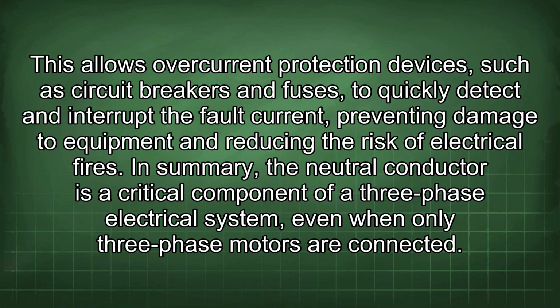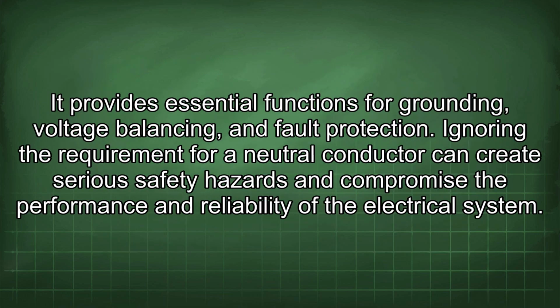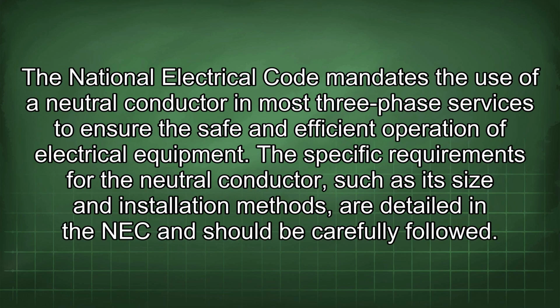In summary, the neutral conductor is a critical component of a three-phase electrical system, even when only three-phase motors are connected. It provides essential functions for grounding, voltage balancing, and fault protection. Ignoring the requirement for a neutral conductor can create serious safety hazards and compromise the performance and reliability of the electrical system. The National Electrical Code mandates the use of a neutral conductor in most three-phase services to ensure the safe and efficient operation of electrical equipment.